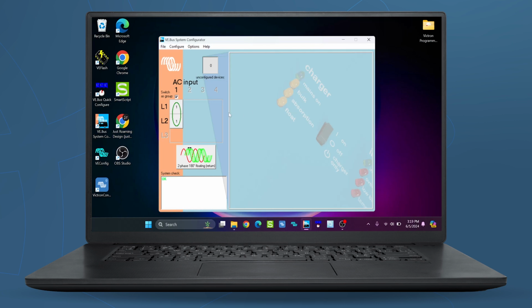Unlike on a parallel configuration, now we can see that there's one unit present on each line: line 1 has 1 unit, line 2 has 1 unit. And these are switched as group. We want to unselect switched as group for most applications, especially on the RV side of things. By turning off switched as group, it allows us to plug into a 120 volt system or a 120 volt pedestal and still have full operation of the units.